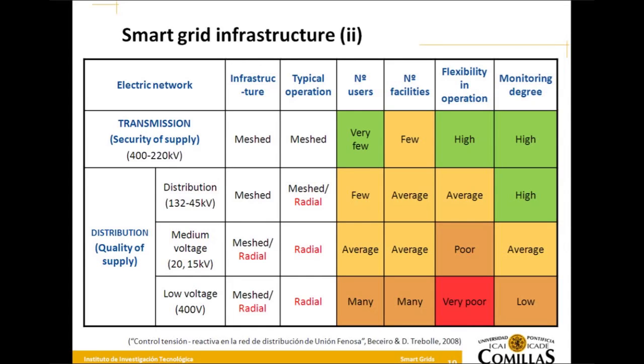The smart grid infrastructure is very complicated. In the current traditional grid, if we look from the higher transmission level to the low voltage, squares in green indicate areas that are easy to operate, manage, and monitor. However, as we go down in voltage levels, the degree of monitoring and operation quality becomes very poor. This is critical because all new distributed energy resources will be connected at low or medium voltage — levels that are currently poorly monitored and where operation is difficult and not flexible, often requiring manual intervention on-site.